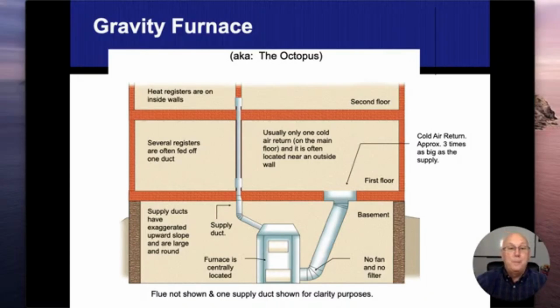The fire would burn, heat up. It would get that cast iron refractory pot super hot. The circulation air would be on the outside. And as I mentioned earlier, we don't have a blower fan on these, so it worked on the principle of convection with hot air normally rising. So the hot air would start to rise. We would have our registers, our grills, our diffusers, whatever we had, they would be in the middle of the home. So the hot air would have the shortest, straightest distance going up, and then that would start dumping into the rooms. Usually I would have one central return that comes back down on these things.